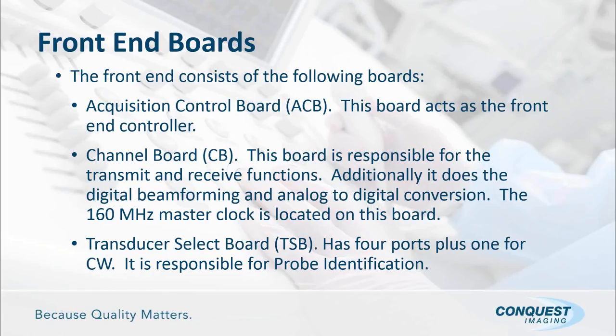Multiple probes, multiple ports. And if you eliminate the fact that it's not the probe, and let's say you ordered a transducer select board and it didn't fix the problem, there's really only one other place it can be, and that's going back to the acquisition control board, because that's what reports the identification of the probe to the back end. So you're really in the front end looking at only 3 possibilities, the probe being the easiest one to eliminate.